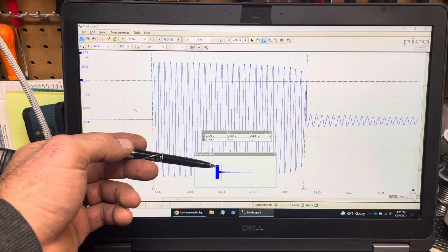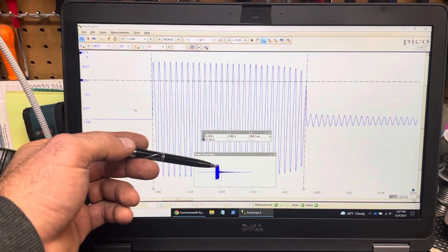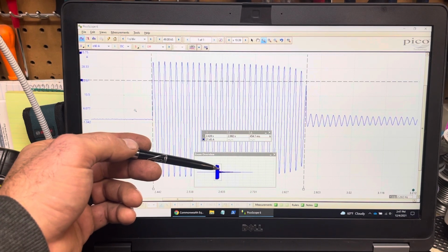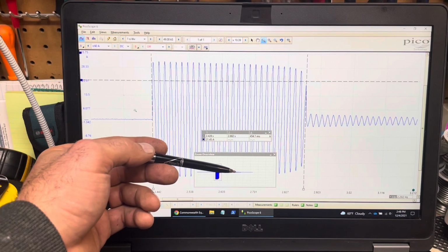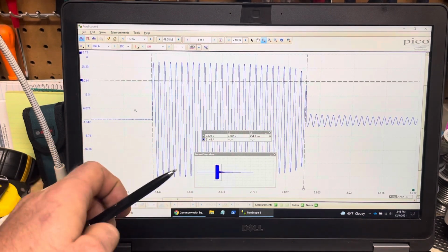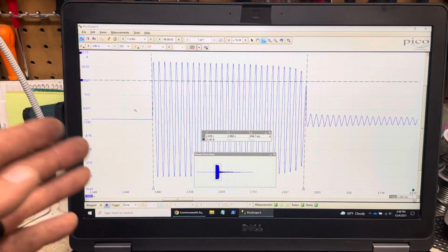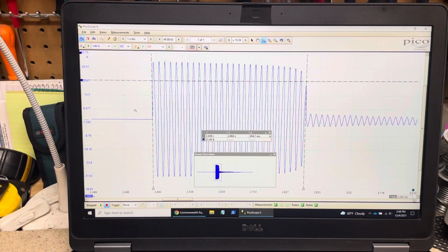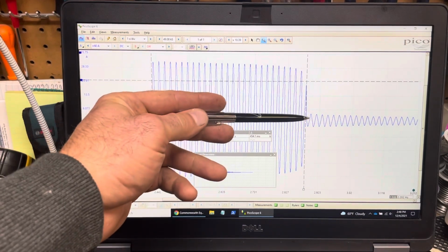So you can see that initially the PTCs allowed a lot of current, and then that current begins to taper off and eventually goes to 0. What's happening is the PTCs are heating up and the resistance is increasing, but it's not instantaneous. So they taper the current off and eventually get hot enough where they pretty much go open circuit. You can see that detail here.